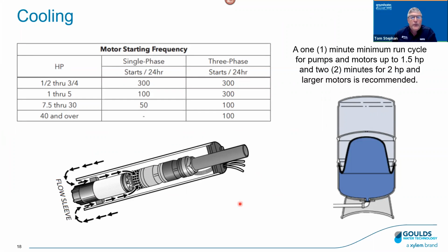Okay, so let's get back to cooling a little bit. Most of your motor manufacturers will give you some sort of chart in terms of maximum starts per hour. This is just one example here, and it gives you some limits. It's based on horsepower, and we can see here single phase versus 3-phase, and this is starts per 24 hours. Normally that's not much of an issue, but it's a good thing to pay attention to. And again, what is the issue with that? When you start a motor, certainly fixed speed, you give it startup amps, which are high amps, and high amps mean high heat. So that's really the concern here. And notice that this starts per 24 hour number goes down as the horsepower gets bigger, right? Because you have more amperage.